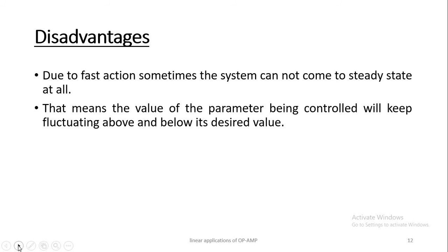Next are the advantages of the proportional controller. The main advantage of the proportional controller is its fast speed of response, and the second is that the change in output takes place as soon as an error is produced. Now, the disadvantage of the proportional controller is that, due to the fast action, sometimes the system cannot come to a steady state at all. That means the value of the parameter being controlled keeps fluctuating above and below its desired value.